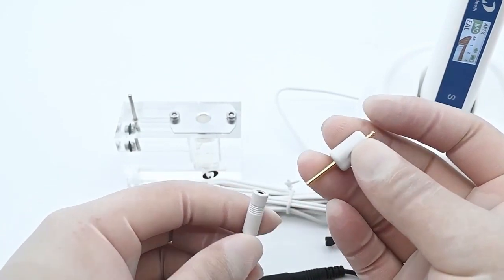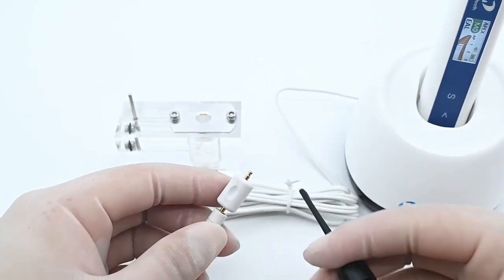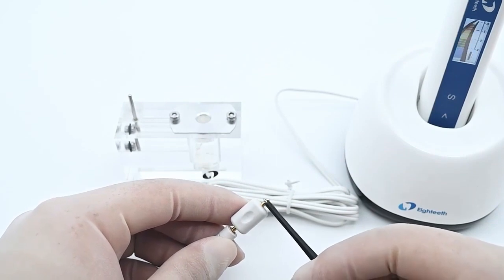Use the Apex Tester to check the accuracy of the Apex Locator every time before use. Confirm that the highlighted value must be between 01 and 03.